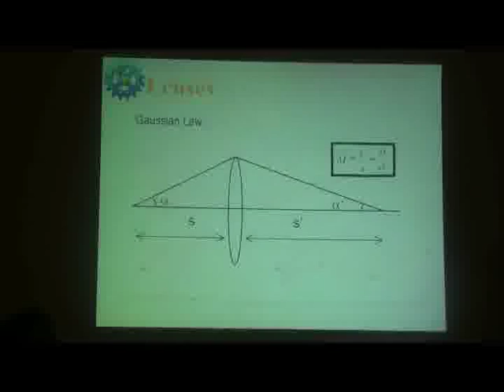This is a simple Gaussian formula, and basically what we are looking at is how the electron beam generated from the source is demagnified so that you get a very small spot size on the specimen. How much you can demagnify is very important, because that depends on the resolution. If you have a very big spot size, your resolution will be very poor. So how much you can demagnify using these lenses is all that matters. Now, we are not looking for magnification, rather we are demagnifying the spot size.